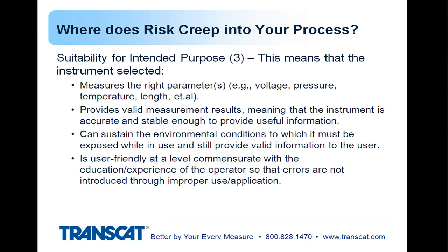So I want to talk about some specific categories here, starting with suitability for intended purpose. Again, when you're looking at selecting an instrument to make measurements in your production process, you've got to take a look at the parameters that you're measuring in the process and make sure the instrument can measure those same parameters. You also want to make sure that you have a good, accurate product that can make stable measurements for those readings. What environment is it being exposed to? You've got to check that as well as part of the suitability for intended purpose, making sure that the instrument, as stated by the manufacturer, can work in the environments that it's being used in, and that you're checking also to see if there's an impact to its accuracy based on the environment that you're exposing it to.